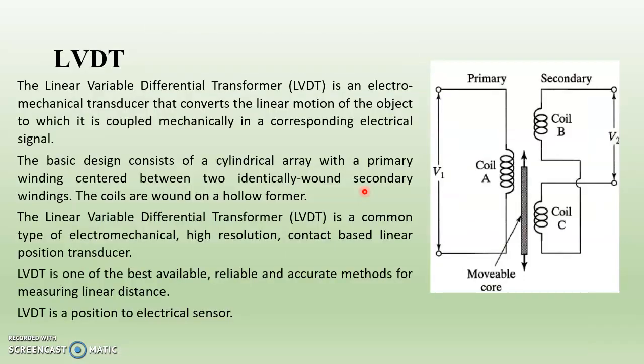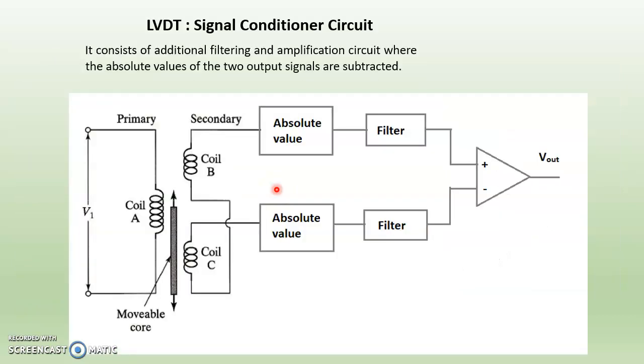Now how does it work? When AC supply is given to coil A, it produces a magnetic field, and in between secondary coils B and C there is a movable core. When this core moves in this space, there is a change in the EMF induced in coils B and C, measured as V2, which is taken to the electronic circuitry for signal conditioning. The difference between these two voltages is monitored at the output, so whatever position change occurs, there is a corresponding change in the secondary voltage.